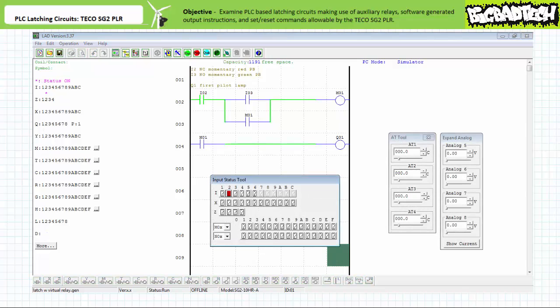Using the TECO SG2 client programming software simulator utility, let's examine the behavior of this program in response to simulated field input devices in various actuation states. Note the simulator's default start state assumes all switched input devices are normally open, so before initiating simulation one must toggle the simulated field input device attached to input I2 to closed to more accurately reflect our as-built system. In the deactivated state, the make instruction examining I2 permits logical continuity; however, the make instruction examining I3 does not permit logical continuity onto the coil of auxiliary relay M1.